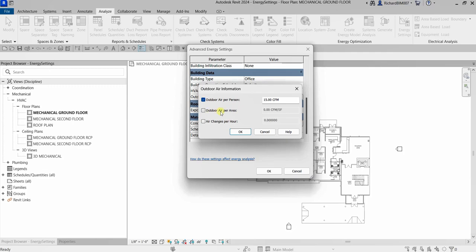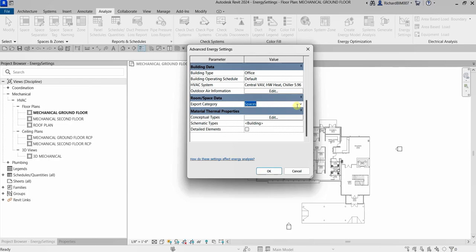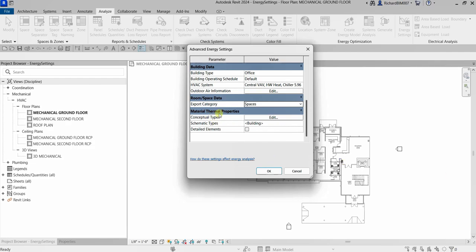You also have Outdoor Air Information — click Edit to specify outdoor air per person, outdoor air per area, and air changes per hour. You can also specify the Room/Space Data Export Category. When set to Rooms, Revit passes the room object name and number to the corresponding analytical space. When set to Spaces, Revit passes the space object name, number, occupancy, lighting, equipment, and zoning.